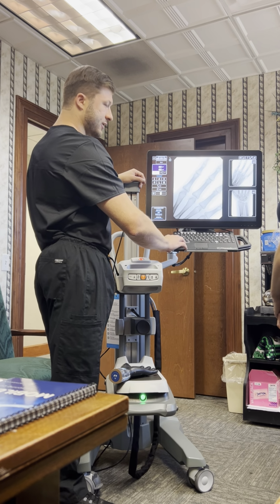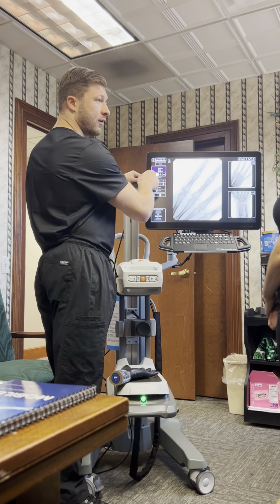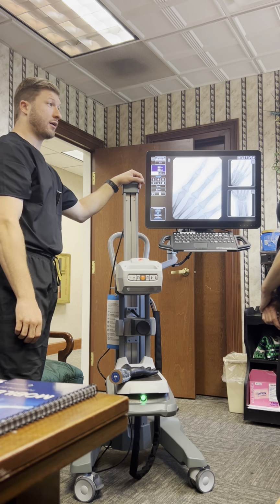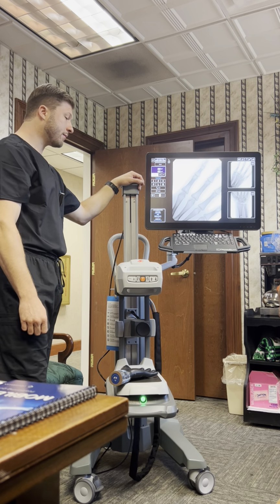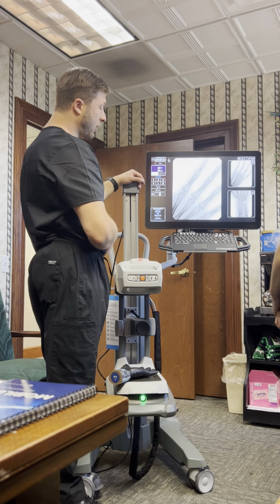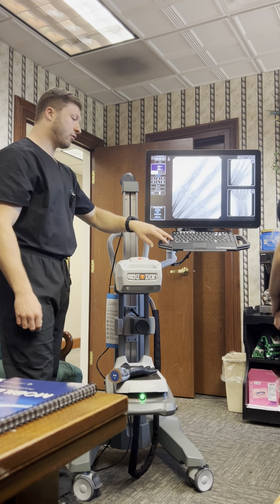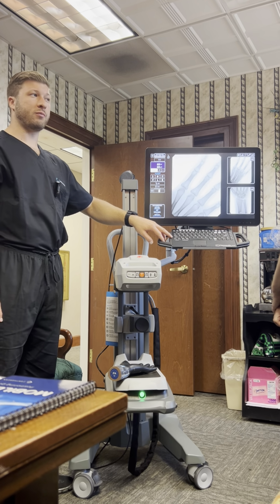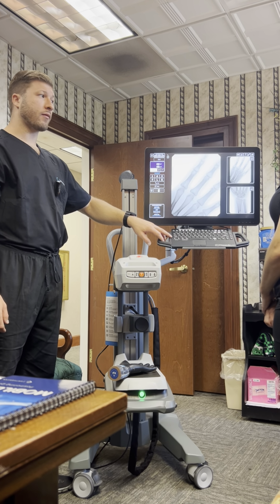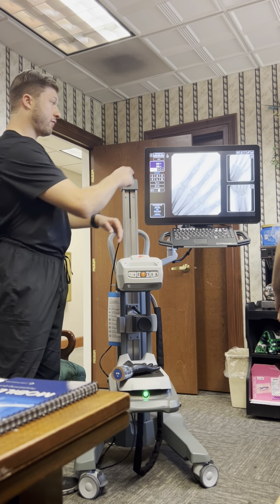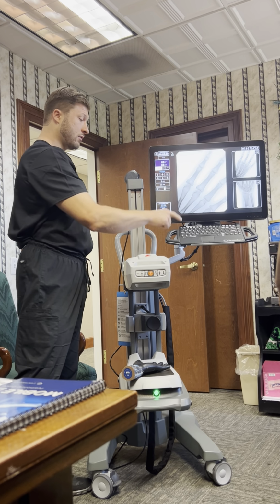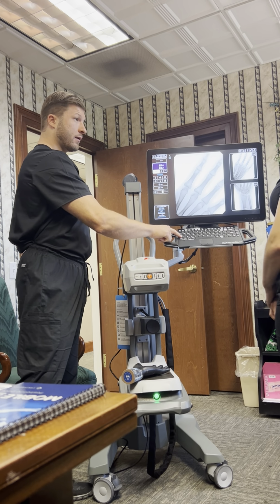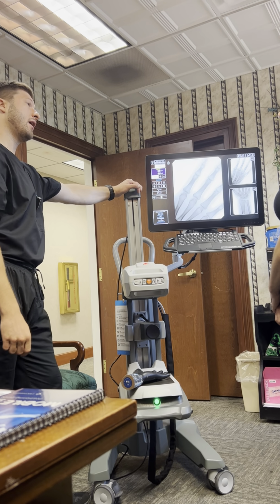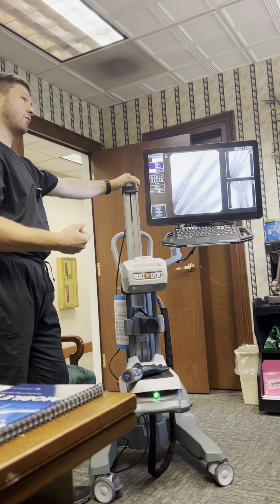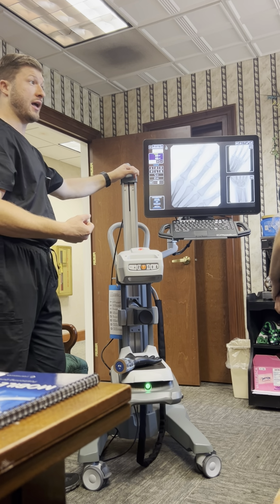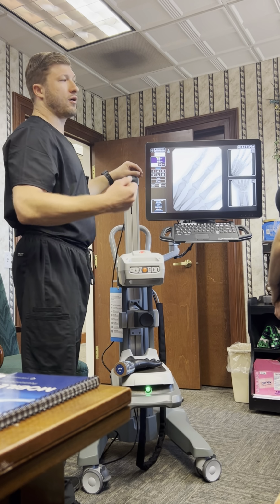Again, we can manually adjust the kVs here, but it's in auto, and I recommend keeping it there so it can recognize the density of the anatomy. But again, you can manually adjust it if you want. The only time where we're thinking of radiation exposure, I guess, or mitigating a ramp up time to get from low kVs to high kVs, is the boost button. Is that like a mag image? So yeah, you could almost say that it allows the device to reach its maximum kV level of 78 kVs. It's not going to go straight up to it.